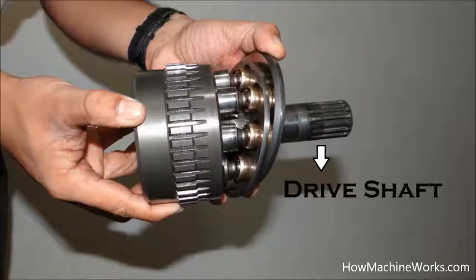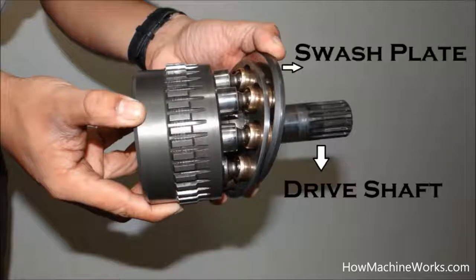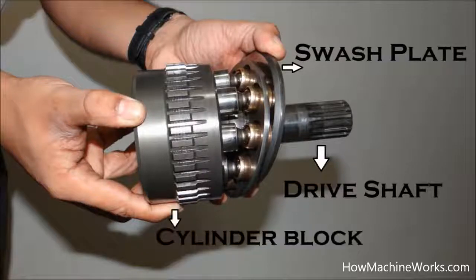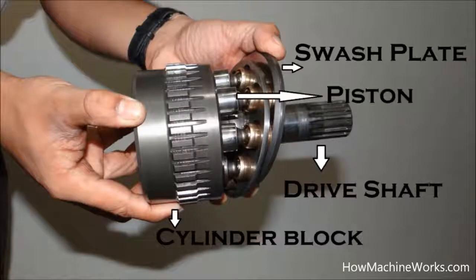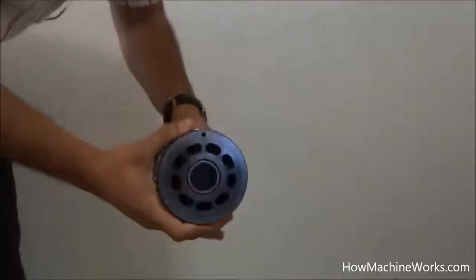That's the drive shaft, which is a part of the cylinder itself. The drive shaft gives drive towards the cylinder, and that's the swash plate, which I told the pistons are resting and sliding over. When the swash plate angle changes, the flow varies. That's our cylinder block in which we have the pistons arranged, and as the cylinder block rotates, the pistons slide over and axially reciprocate. That's the pistons over there. We have many pistons arranged inside a particular cylinder block.